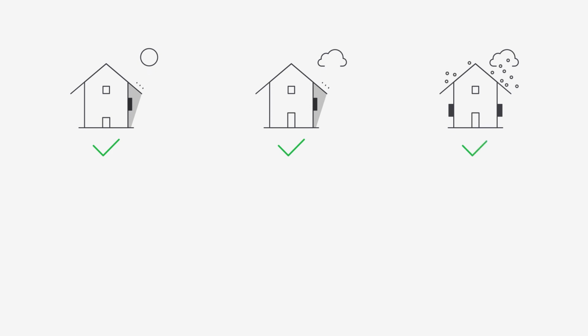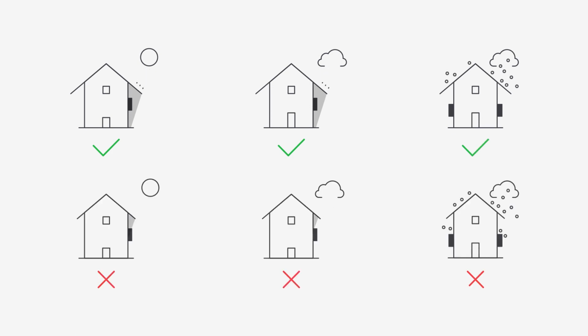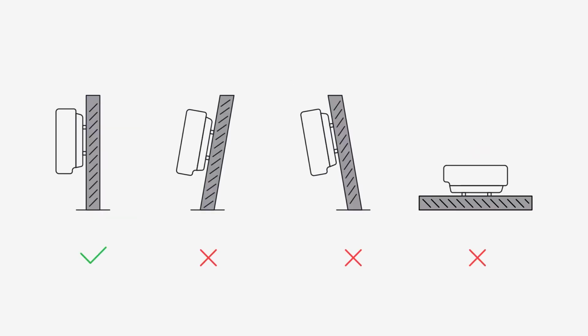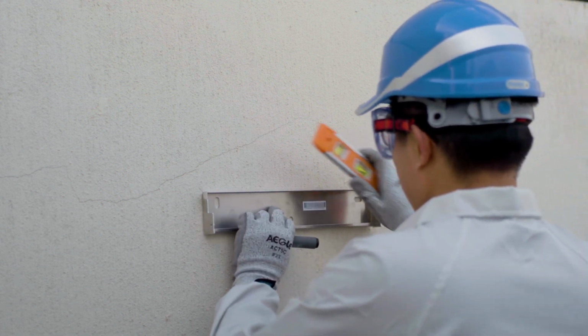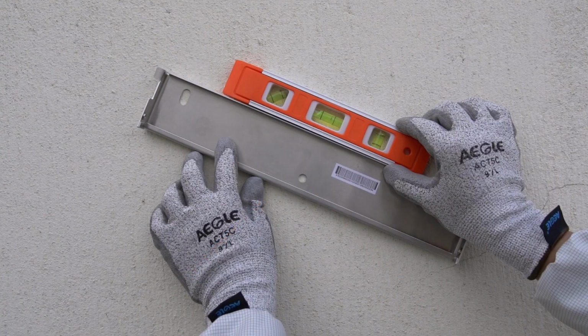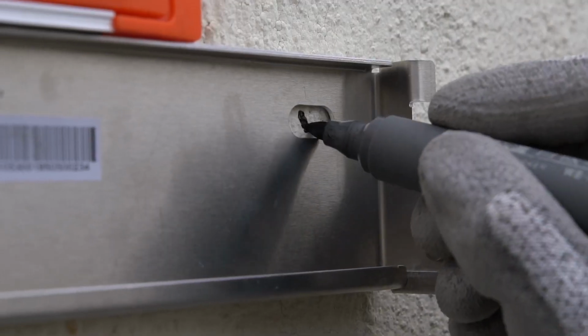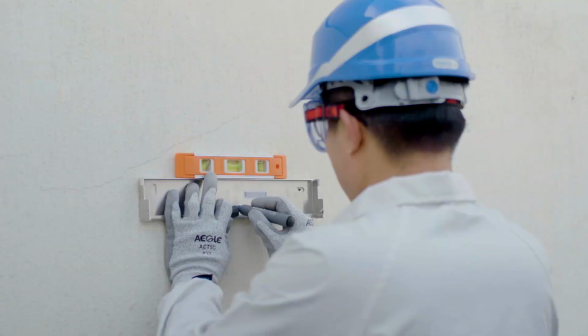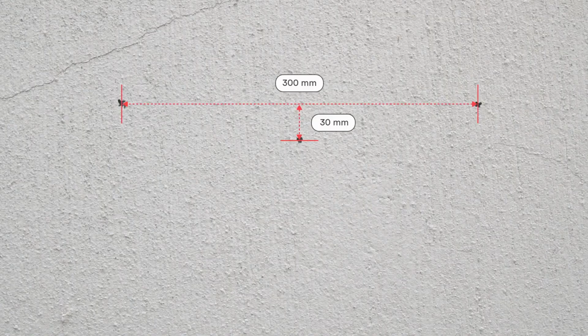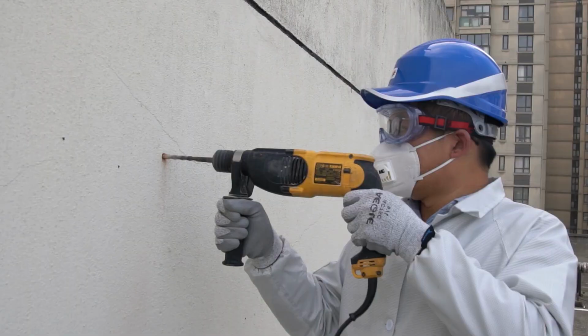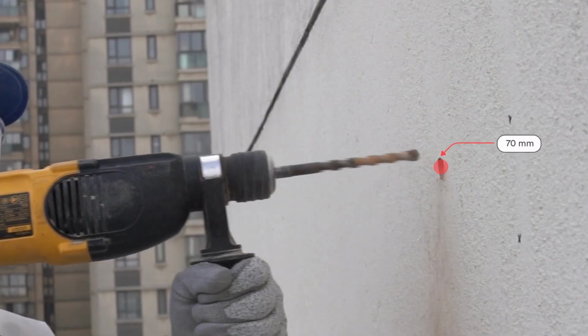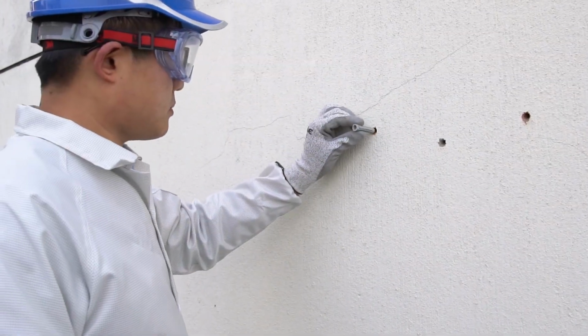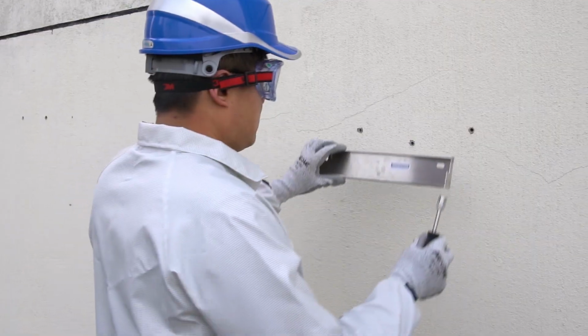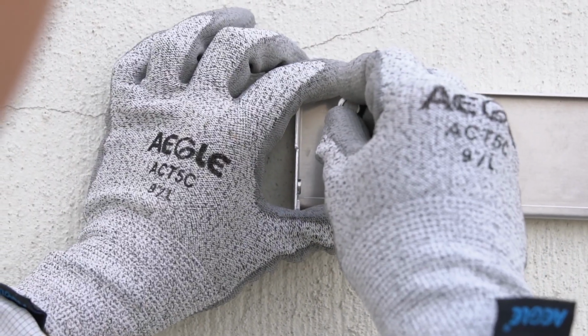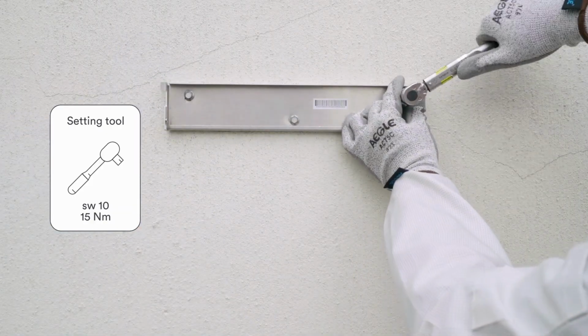Avoid exposing the inverter to direct sunlight, rain and snow to ensure optimal operation and extend service life. Mount the inverter on a vertical wall. Position the wall bracket horizontally. Use the wall bracket as a drilling template and mark the positions of the drill holes. Drill holes with a drill. After drilling holes in the wall, place screw anchors into the holes. Then, attach the wall mounting bracket to the wall using the self-tapping screws delivered with the inverter.